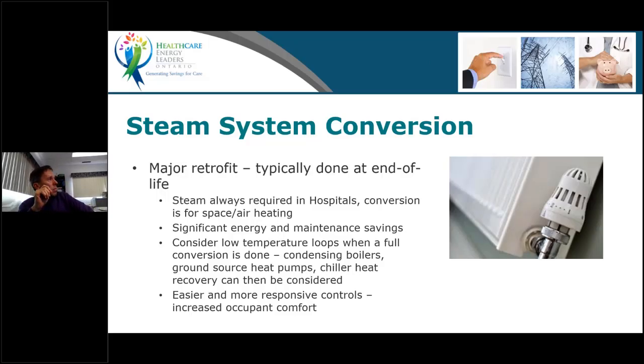When you're thinking of a major retrofit, obviously, I think in module 12 we have a presentation of a case study, and we'll talk slightly about that, where they converted a steam heating system in a hospital to a hot water heating system. That will achieve fairly large savings, not just because of the boiler efficiency, but mostly because of the distribution efficiency, where you control way better with hot water. Your modulation is usually much improved. Comfort conditions can also be much improved.